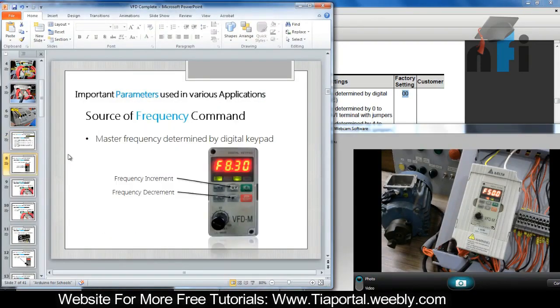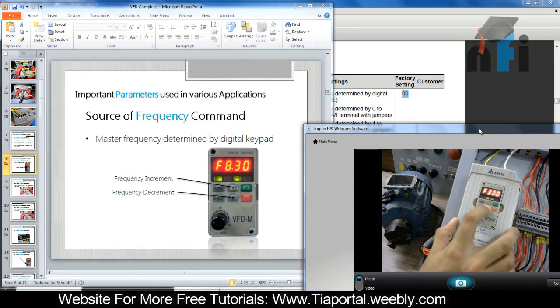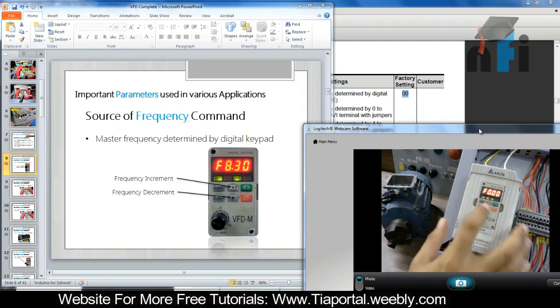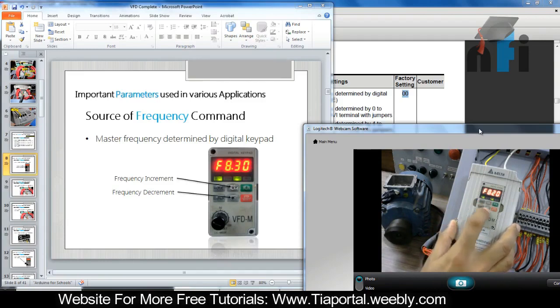Right now the frequency is at 50. I can decrease it using the decrement command - if I keep pressing it, it will keep decreasing. When I press RUN, the motor is running but frequency is 0, so it stops. When I increase the frequency, you'll find the motor starts running - this is 6 Hz. I can increase using increment and decrease using decrement. That's the source of frequency by digital keypad.